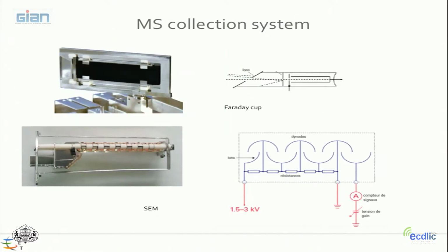So this is what you see if you unmount the Faraday cup and look at the interior. This is graphite, typically just a graphite housing with a tiny hole here. The ion beam is coming inside, hitting the graphite, and then producing current. And you're measuring the current.